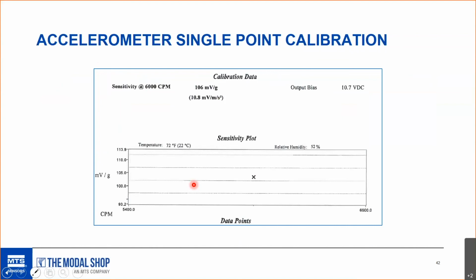Go ahead, Mike. This looks great, though, if you had a sensor and you only wanted to measure at 6,000 CPM. Is that common in industrial measurements? No. That's what I thought. It's unusual to only be interested in that specific frequency. So we have no idea if the sensor is accurate in the high frequency range. If I was using it for gear mesh, I can't tell from this calibration report if it's really accurate for that application. And most turbine OEMs use sensors that are only calibrated at one frequency. Sometimes it's 120 hertz instead of 100, but you only get that one data point. It's kind of interesting that those transducers are mounted permanently on the gas turbine, and they're really your last line of defense for a vibration issue, and they're only calibrated at one point, which doesn't follow the ISO standard.